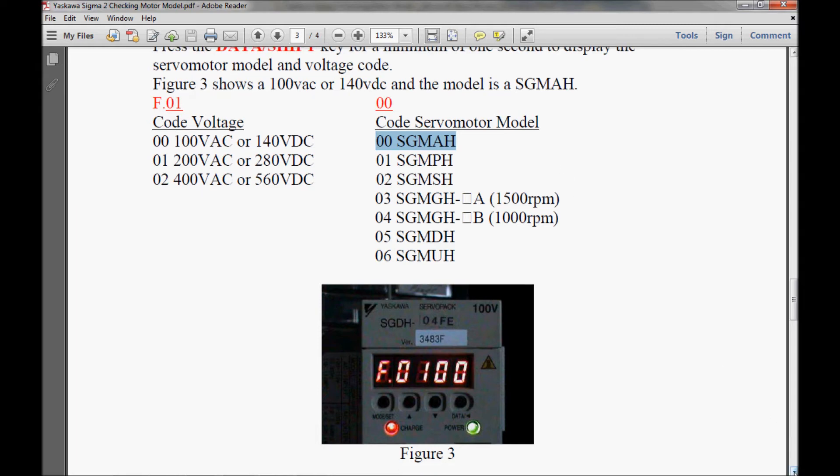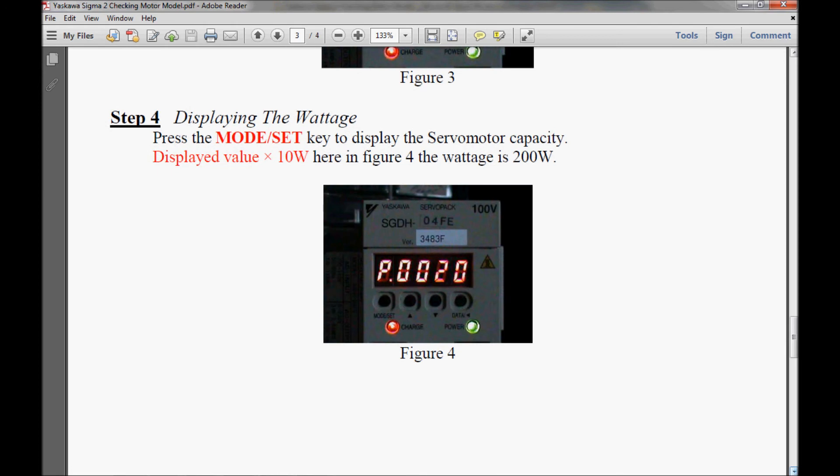I'm going to continue scrolling down here into step 4. In step 4, I am displaying the wattage of the motor. I have to do a little math here. I have to multiply the value that I have here in the display, which is 0, 0, 2, 0. So that's 20 times 10 watts which will give me a 200 watt motor.